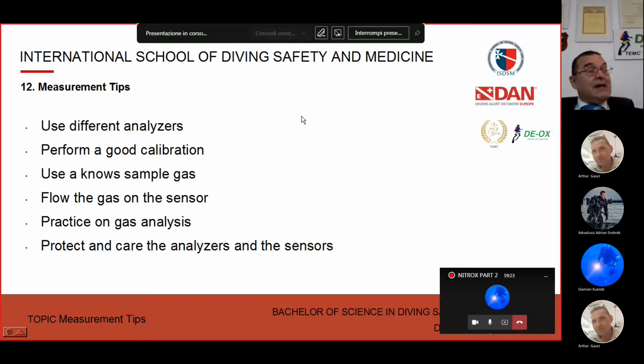Use pure air, flow the gas on the sensor for a long time. As I told you the first time, you start the day's analysis, then go ahead with the gas coming from the cylinder, do the calibration, and then you will have a good sensor and a good calibrated analyzer.